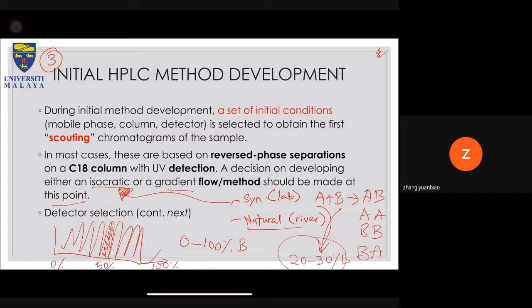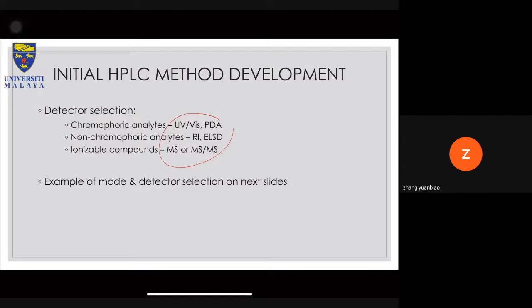So you might want to check, probably for your first scout run, you use UV-Vis, and your second run, you use ELSD, your third run, you use MSMS, and so on and so forth. Each of these detectors has its own pros and cons, its own advantage and disadvantage. As per your assignment, you work with one detector, you know what is the best sample for your particular detector, and you know that there are some disadvantages of your own detector. I'm hoping that you actually include that as part of your writing, not just all the positive things. There's a mark for that comparison, but anyhow, some examples of mode and detector selection are on the next slide.